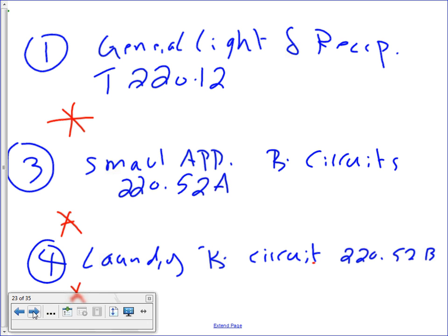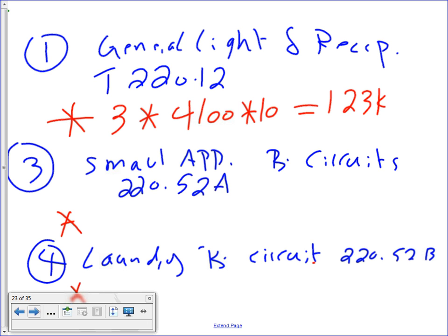Okay, ladies and gentlemen, take the 3 volt-amps from Table 220.12, multiply it by the square footage of this fat, fluffy apartment. Don't forget to also multiply it by 10. Anybody know why 10? Why did we multiply this by 10? That's 10 units. 10 units, an apartment, 10 flats, like the British would say. 123 kVA. So 123 kVA will be allocated, guys, just to the general lighting and receptacles of that apartment building.